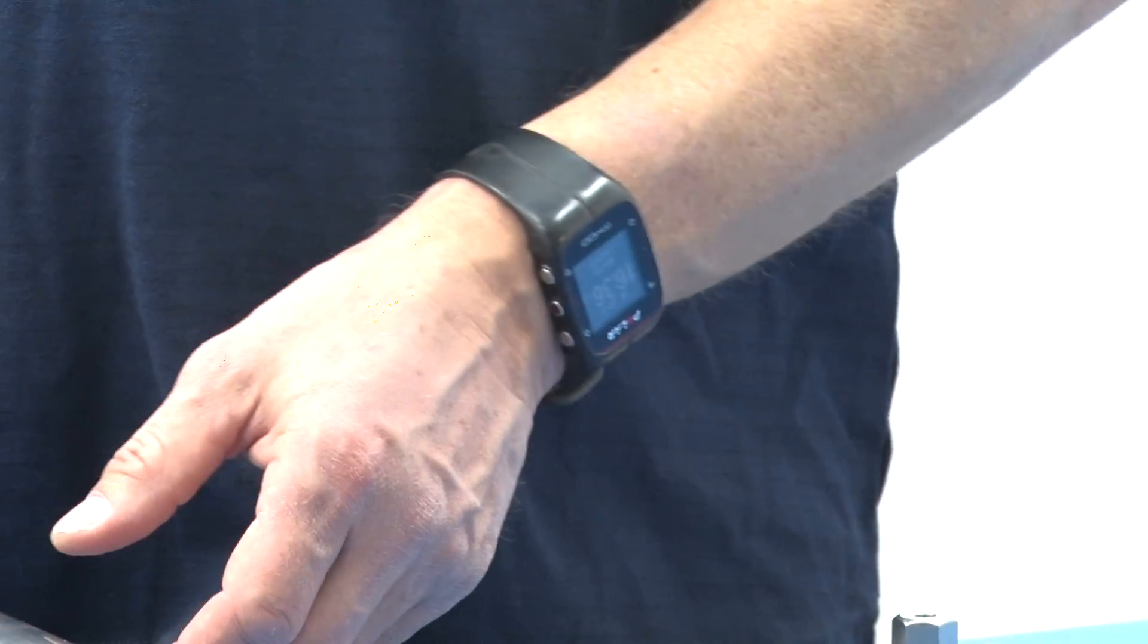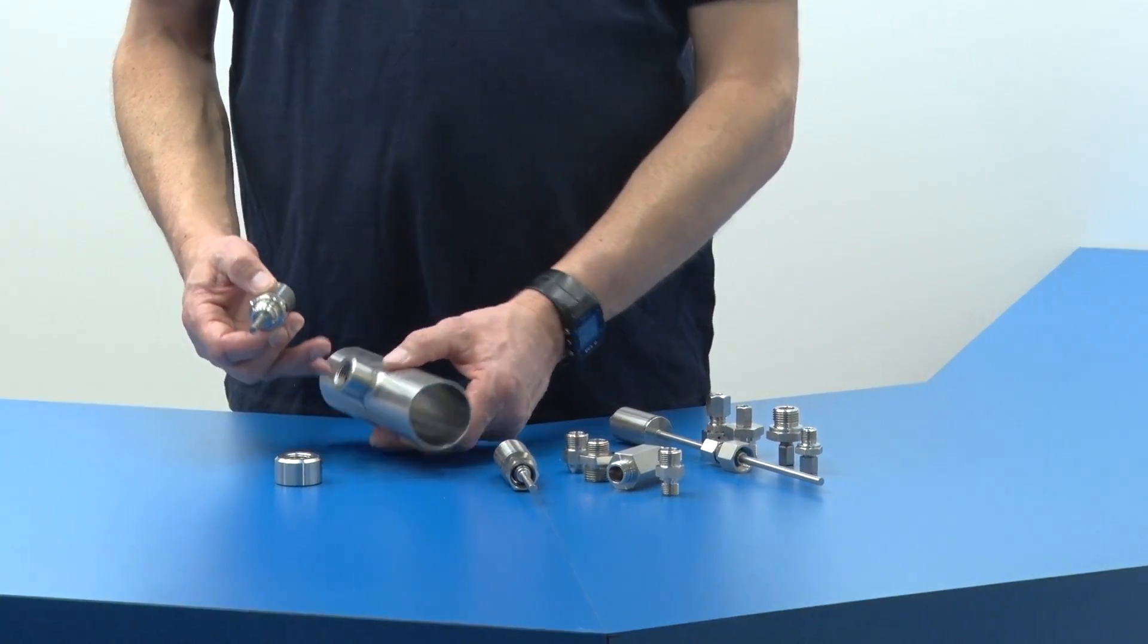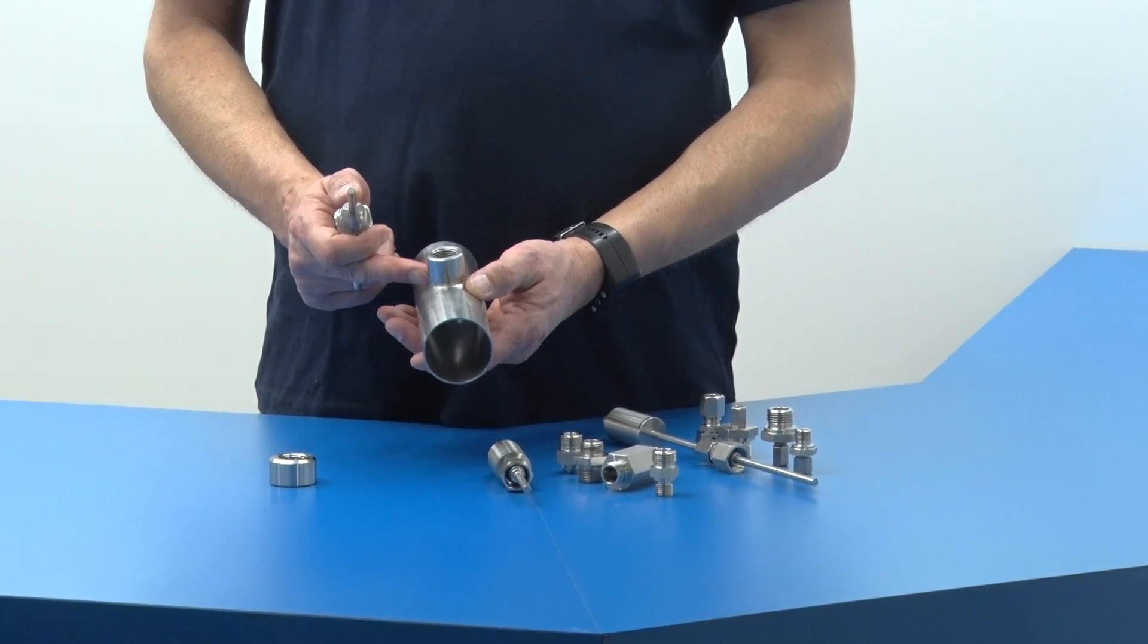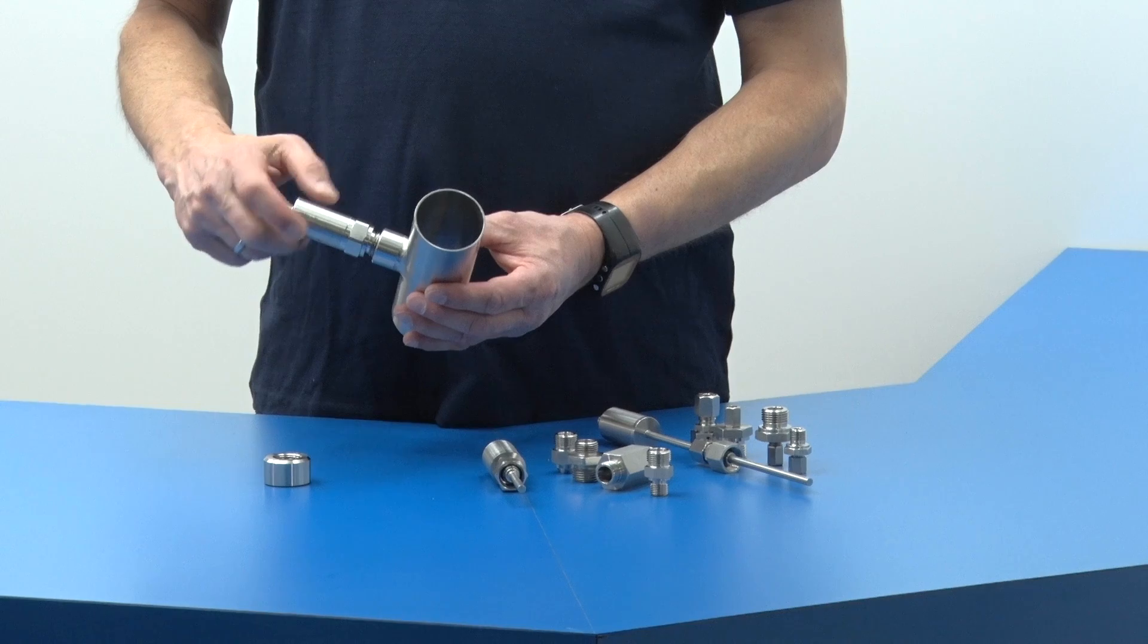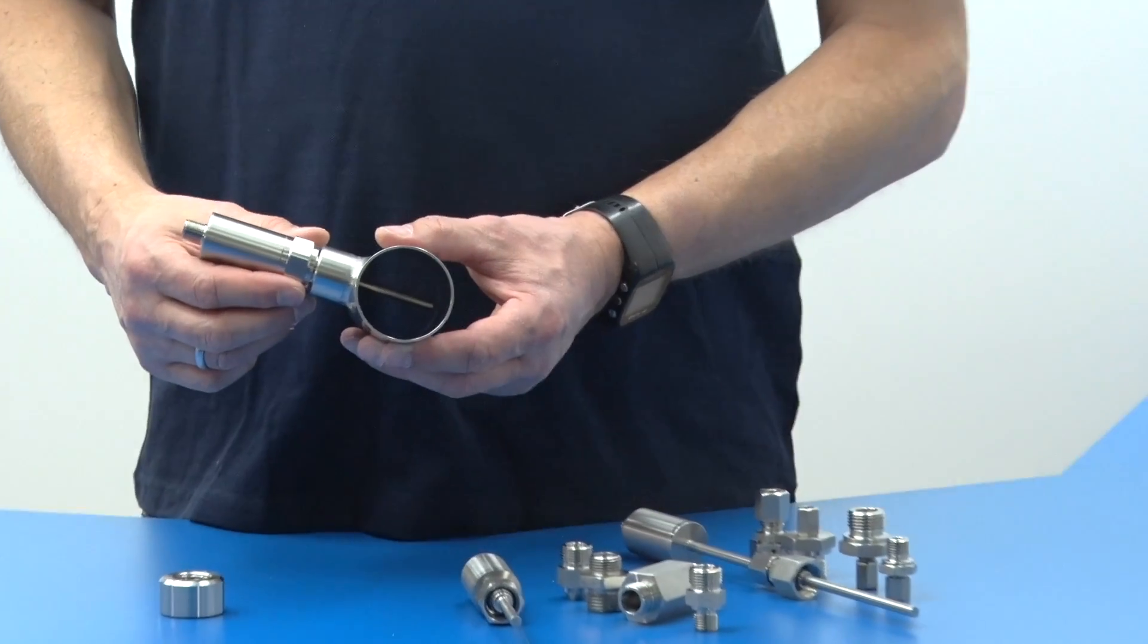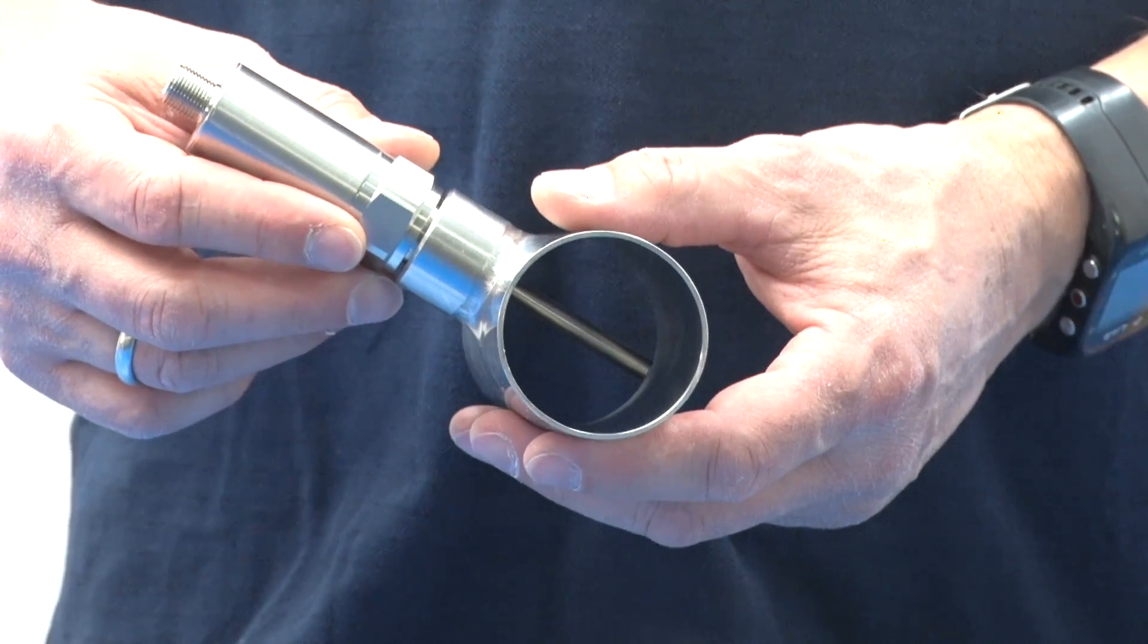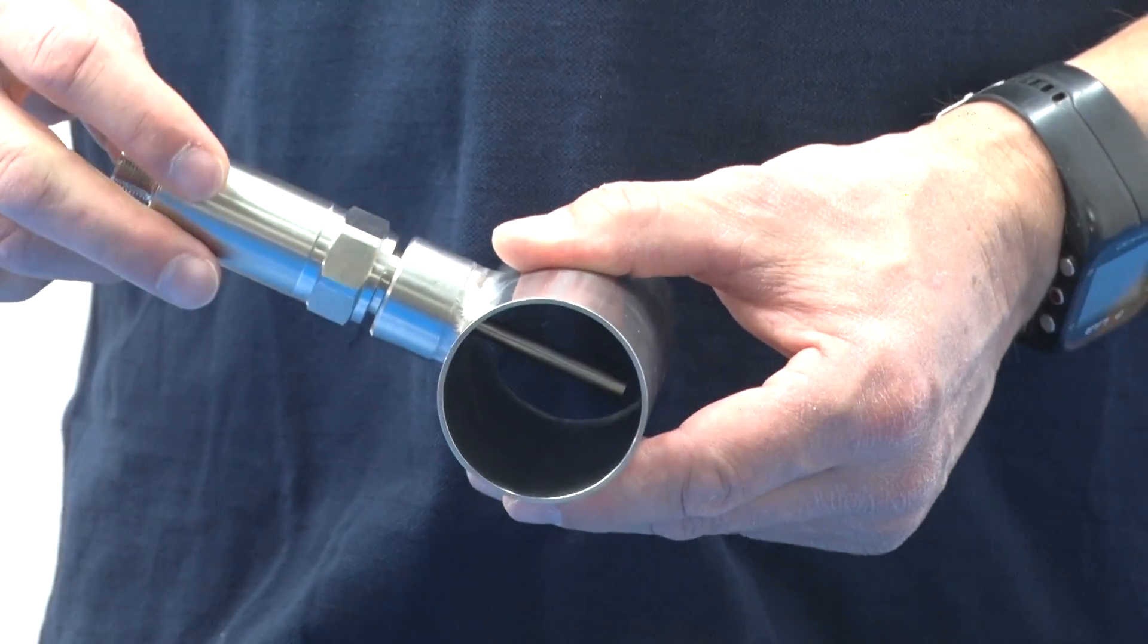G 1.5-inch connection does not require additional sealing, which is a tremendous benefit. Just screw the sensor into the adapter welded on the pipe and tighten to torque. You end up with a tight, all stainless steel connection, which is ideal for use in aggressive media.